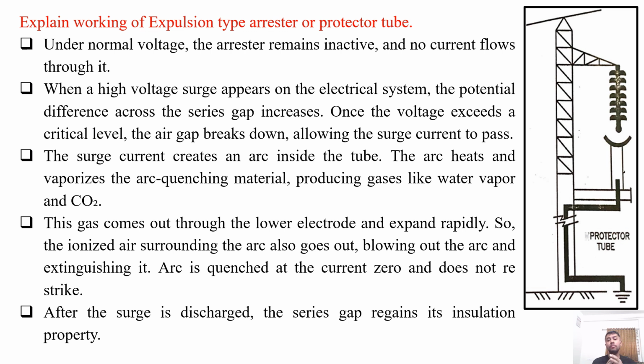Under normal voltage conditions, the arrestor remains inactive, means it is not in conducting mode, so no current flows through it. But when a high voltage surge appears on the electrical system, the potential difference across the series gap increases. Once the voltage exceeds a critical level, the air gap between these two breaks down, allowing the surge current to pass. So surge current will pass through this gap. The surge current creates an arc inside the tube.